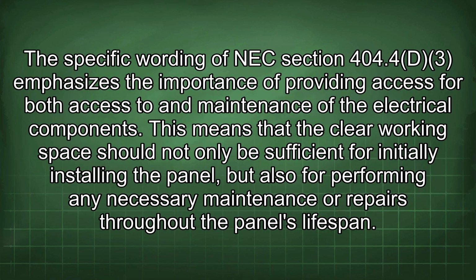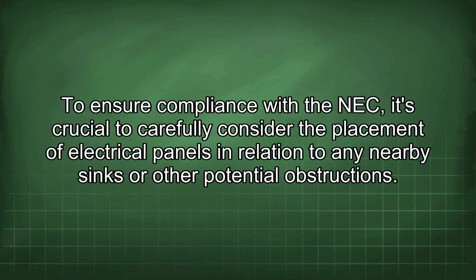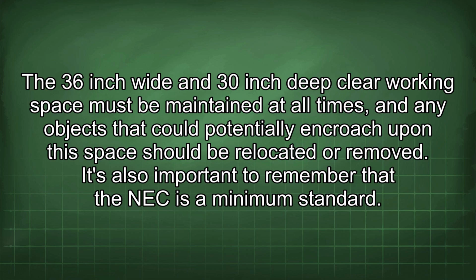The specific wording of NEC Section 404.4D3 emphasizes the importance of providing access for both access to and maintenance of the electrical components. This means that the clear working space should not only be sufficient for initially installing the panel, but also for performing any necessary maintenance or repairs throughout the panel's lifespan. To ensure compliance with the NEC, it's crucial to carefully consider the placement of electrical panels in relation to any nearby sinks or other potential obstructions. The 36-inch wide and 30-inch deep clear working space must be maintained at all times, and any objects that could potentially encroach upon this space should be relocated or removed.